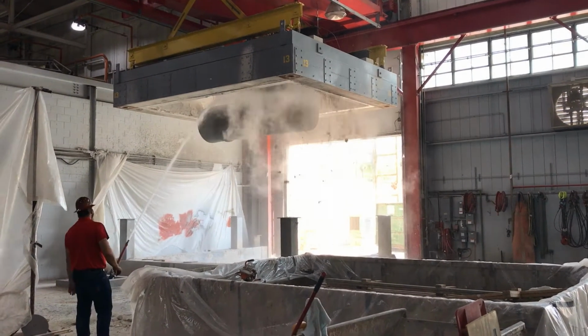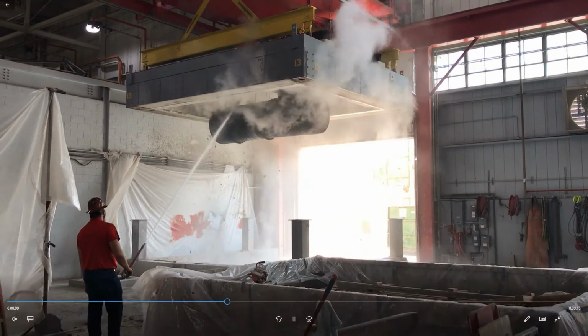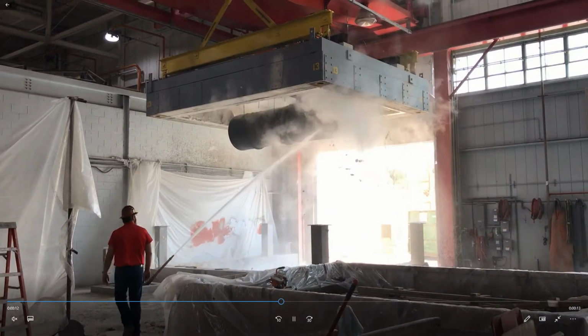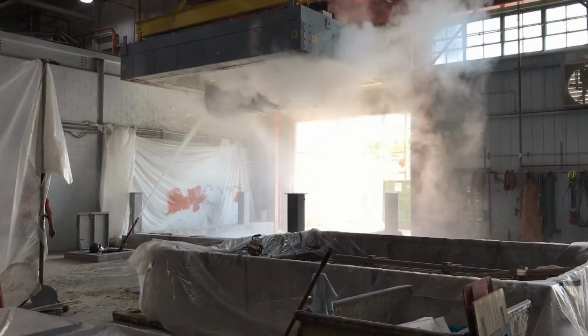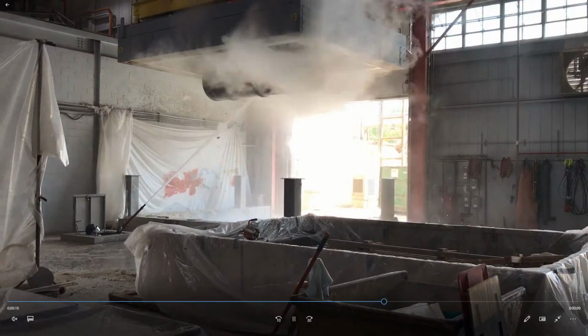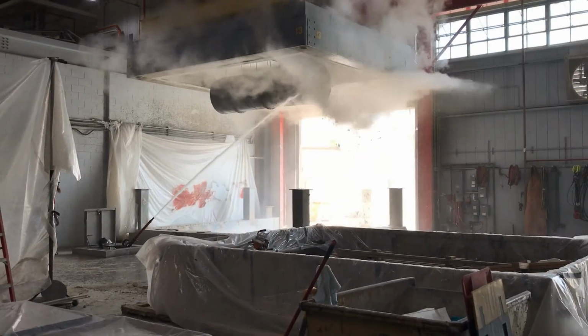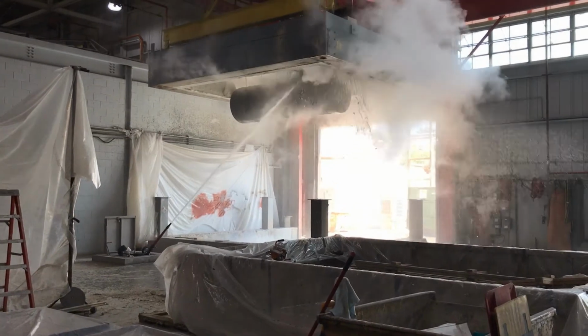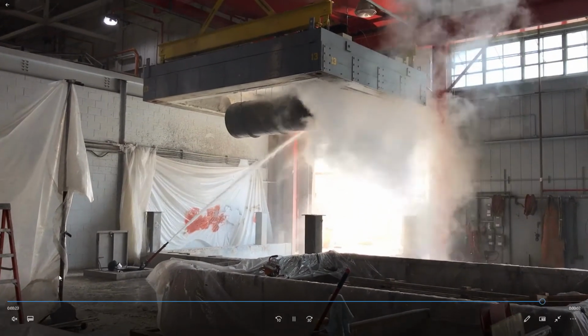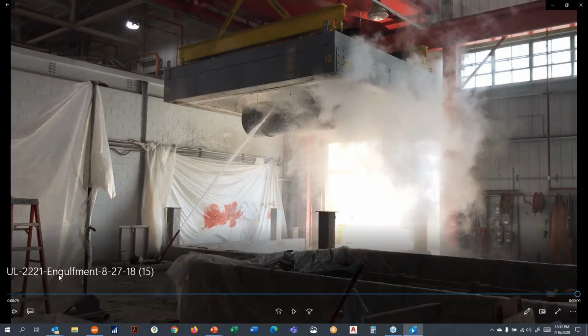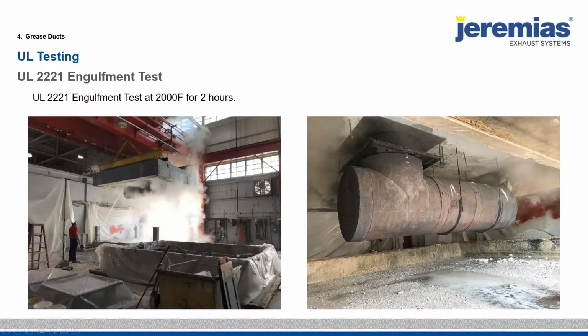So after that, this whole test, the product has to be seen suitable to handle the kitchen exhaust. At the same time, the through wall or through ceiling penetration must have kept the heat intact. So this is a pretty stringent test, a pretty hard test. We can see that a carbon steel system would not hold up very well to this also, but this is a $90,000 test, so I'm not going to just simply go test a carbon steel system to see what that looks like. So this is a very expensive test that all the manufacturers have to go through.